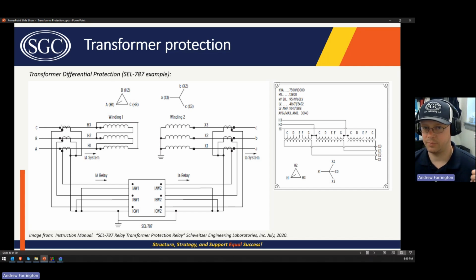You need to look at the transformer winding configuration. You need to look at the phase connections of all the CTs. You need to look at the relay inputs, and all of that is going to go into these compensation settings. This is a simplified example. This is what you're going to encounter most of the time. I just want to make sure that you're aware of those other considerations so that you don't oversimplify it if you're ever asked to set one of these relays.